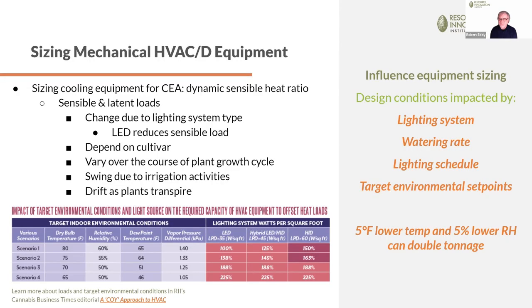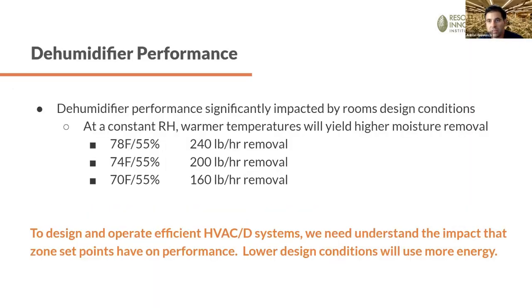That's an amazing statistic, at 5 degrees, 5% doubling tonnage. Yeah, and on the next slide we can see it, I just took a snapshot. This is a 60-ton DX unit, effectively 60 tons of nominal capacity. And you can see we're not moving the relative humidity here at all.